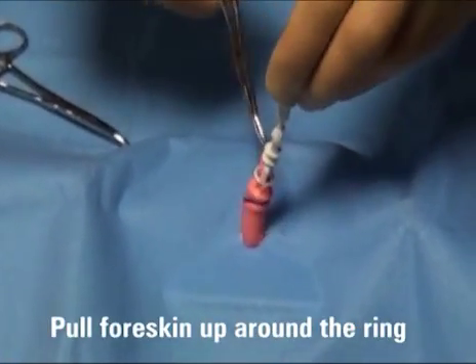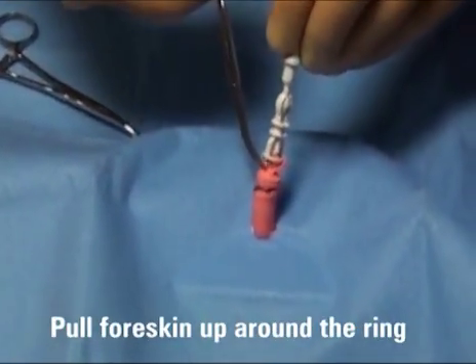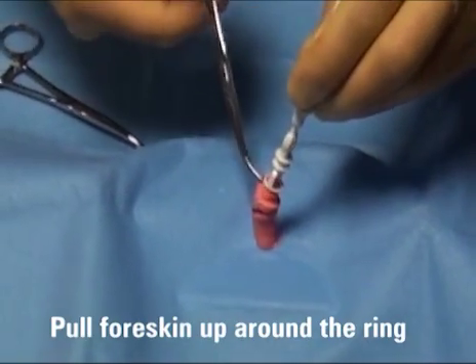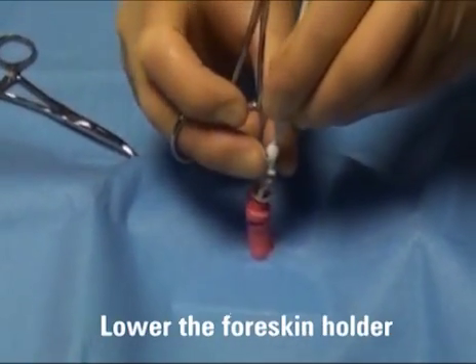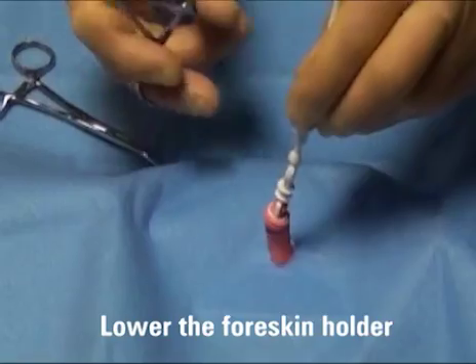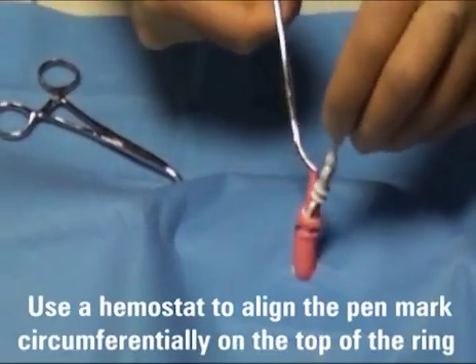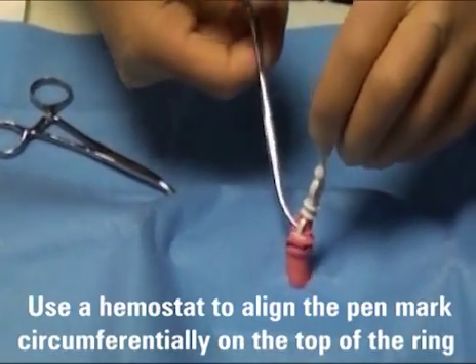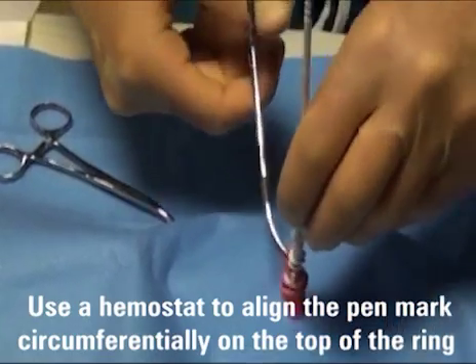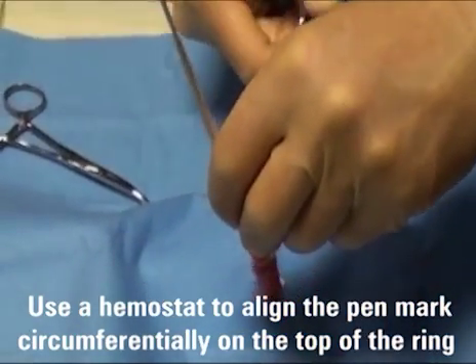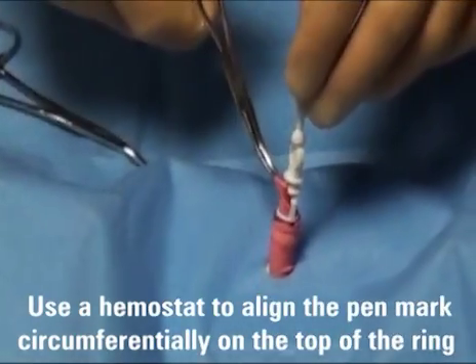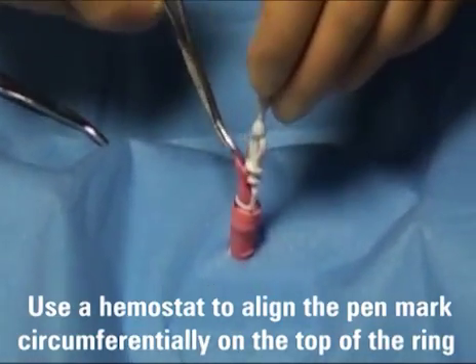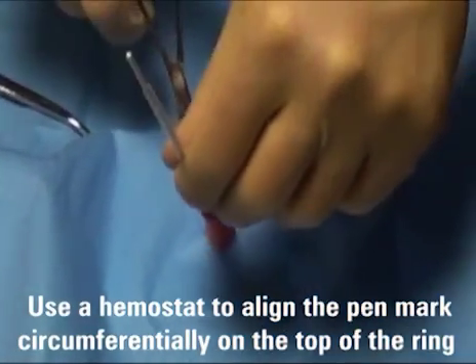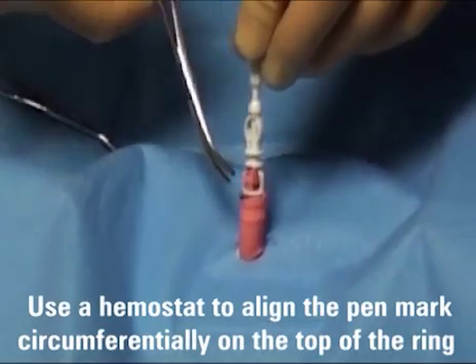Once the ring has been inserted, it can be pushed down on top of the glans and the foreskin pulled up more fully around the ring. Lower the foreskin holder down onto the foreskin to hold it in place. Use a hemostat to position the foreskin so that the pen mark is circumferentially aligned on the top of the ring. Again, the pen mark represents where the incision will be made after the mark is circumferentially aligned on the top of the ring.